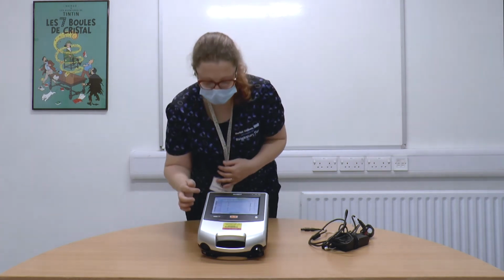The other types of alarm you tend to get are high flow, so you may get circuit disconnection, high minute volume, high tidal volume, high respiratory rate, those all mean that the circuit or ventilator thinks the child is either breathing too hard and too fast, or they think the circuit has come out.